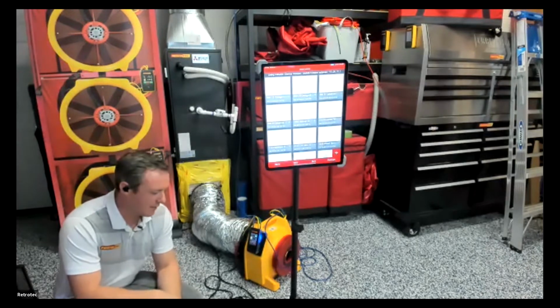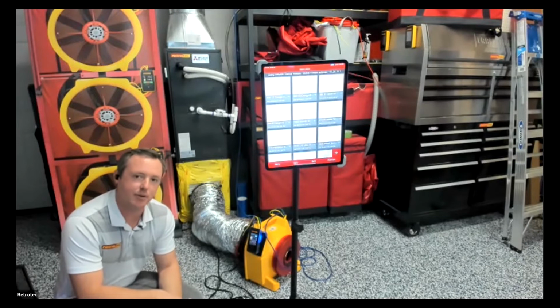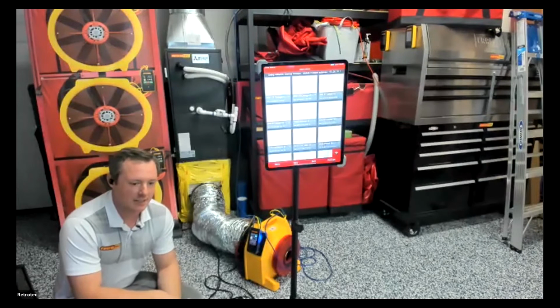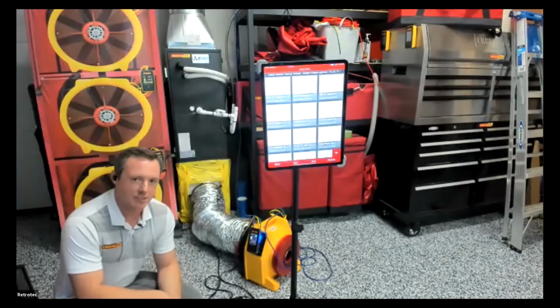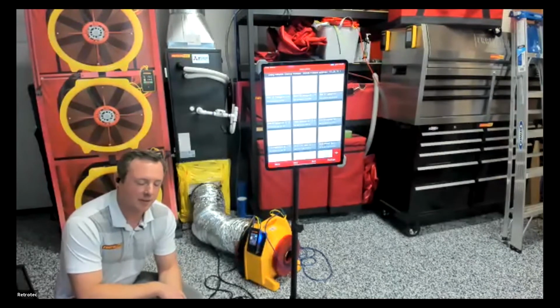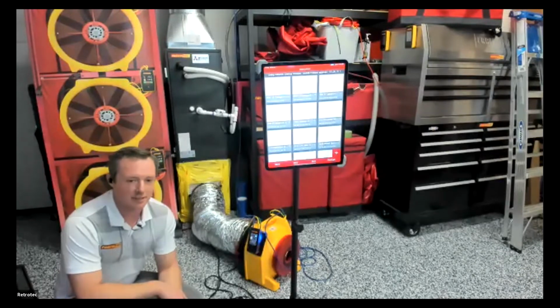And another thing to keep in mind too is we're putting a 25 Pascal pressure on the duct system. Most duct systems, if you have a single stage system, an ideal operating static pressure is 0.5 inches of water, which is about 125 pascals. So it's a lot less pressure than the system experiences when it's running.